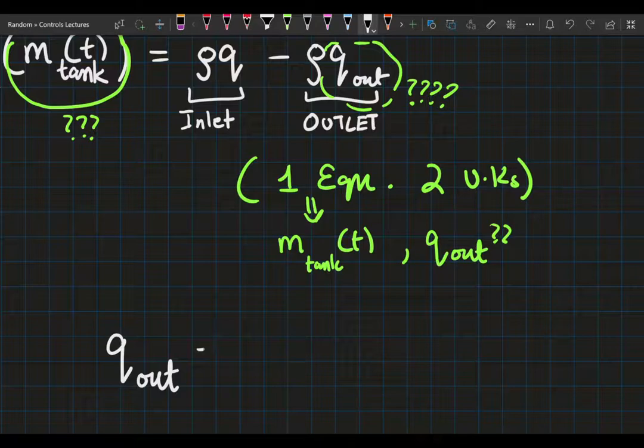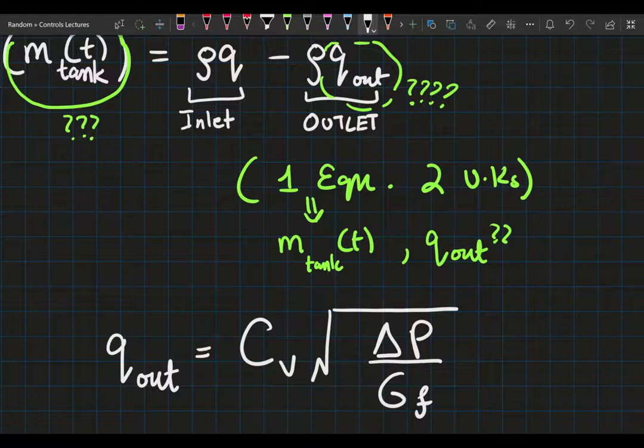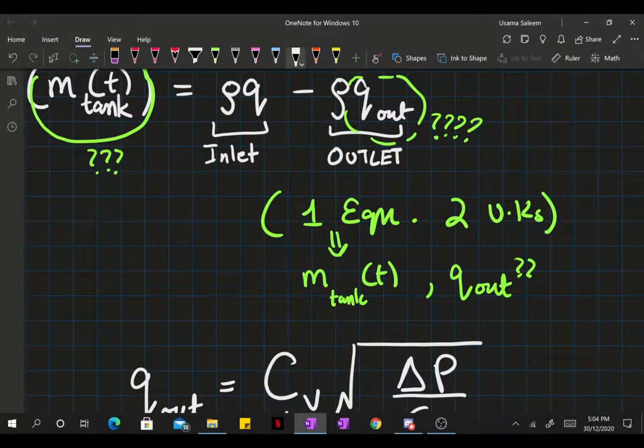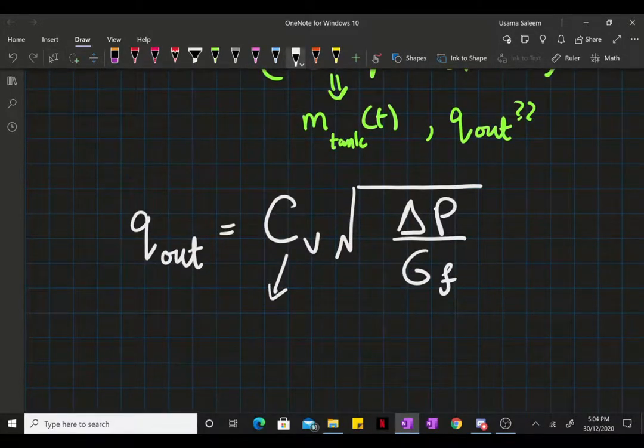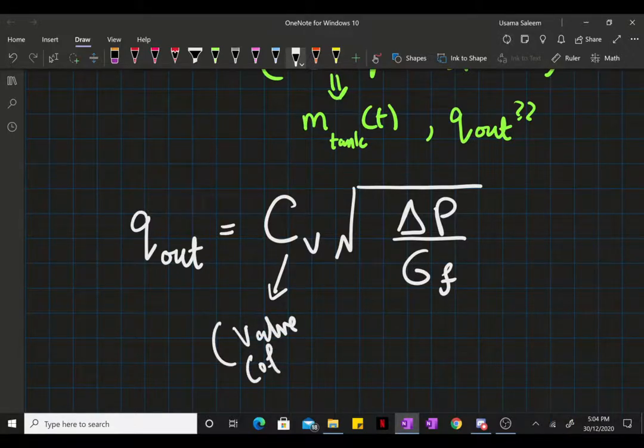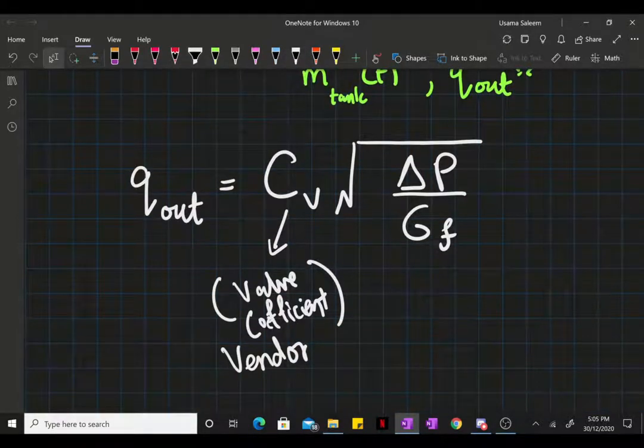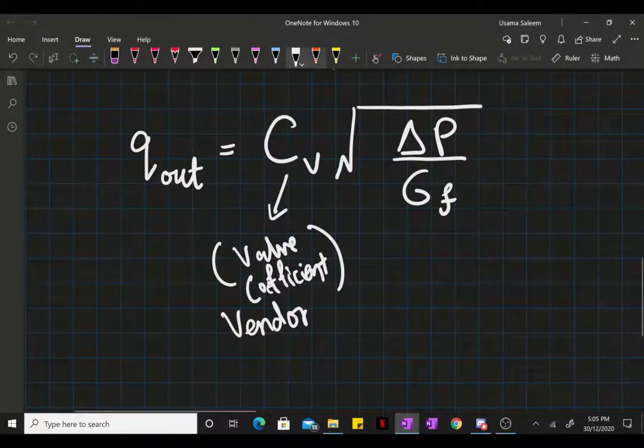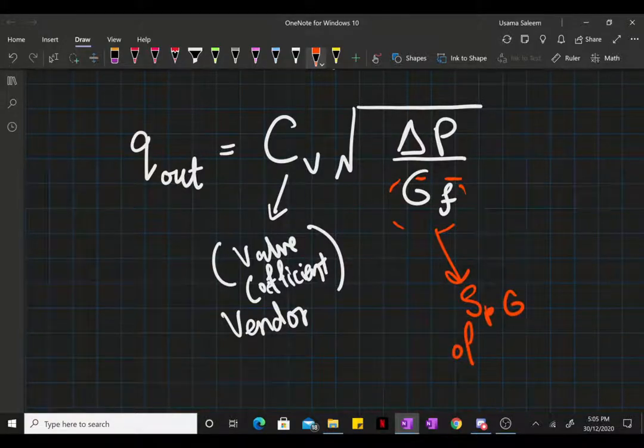Most commercial valves, their discharge flow rate, can be modeled by this concise and very simple equation. We have the valve coefficient, this will be given by the vendor, and the valve model characteristics are going to determine that. We have the specific gravity SG of the fluid that we have.